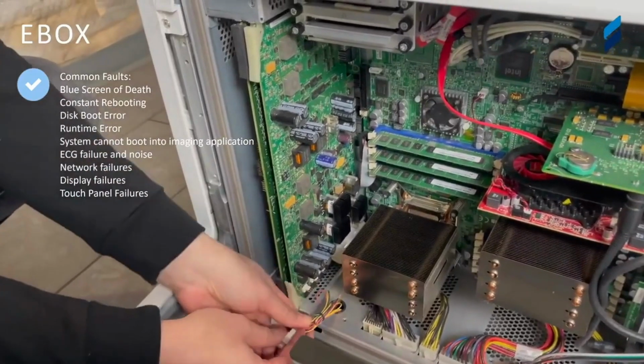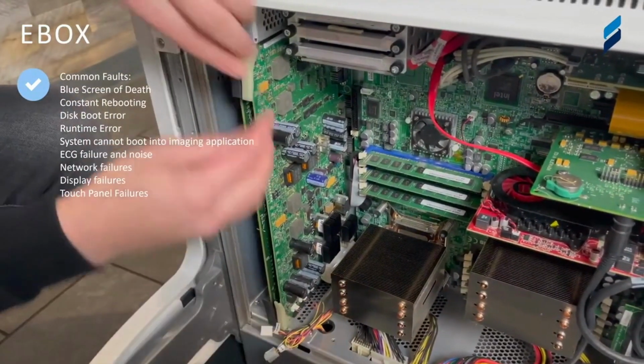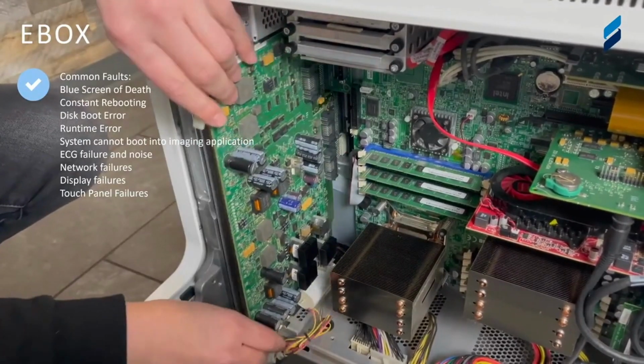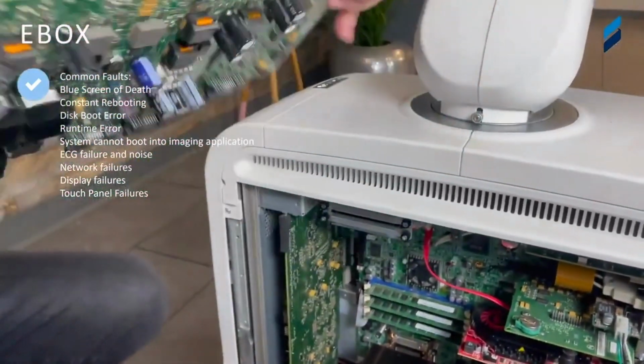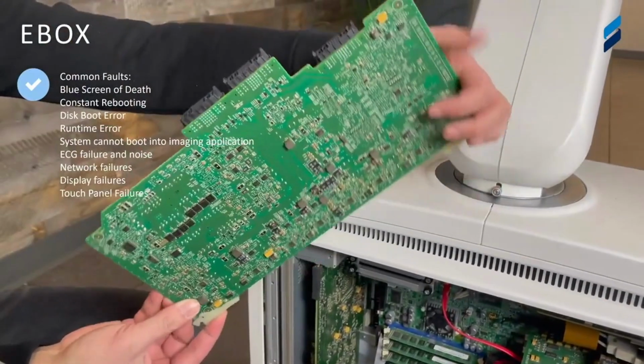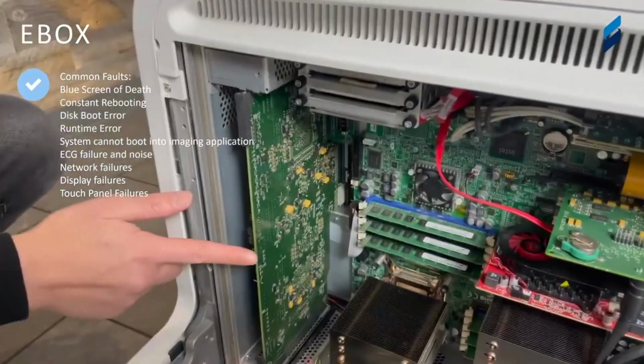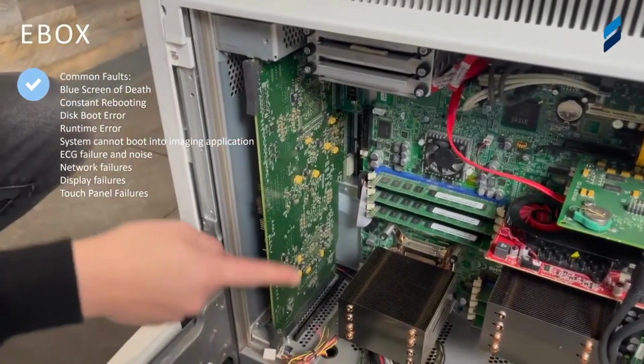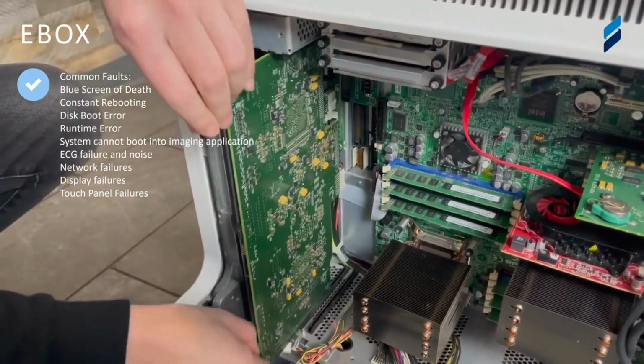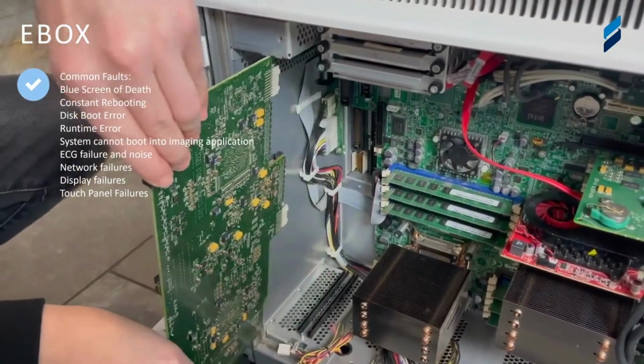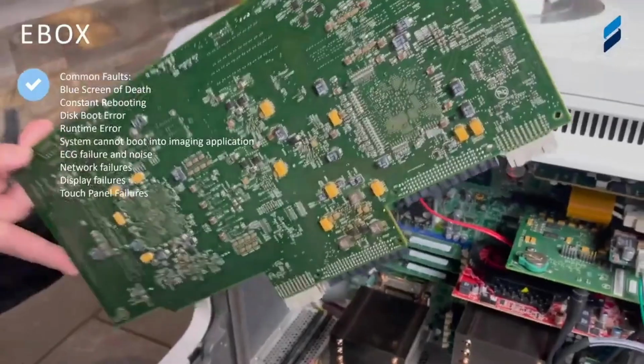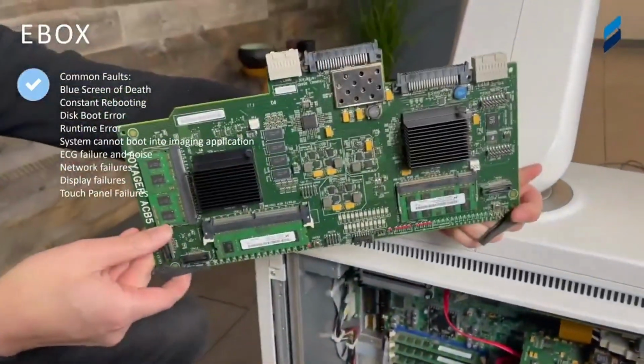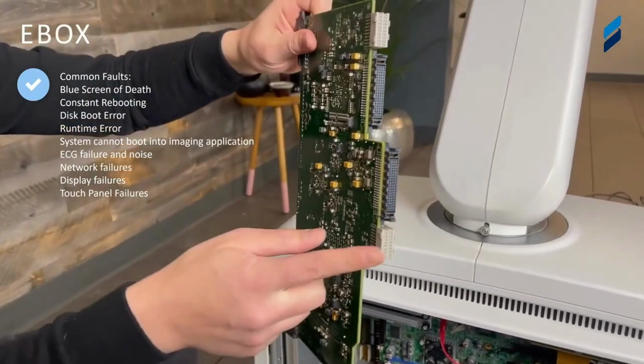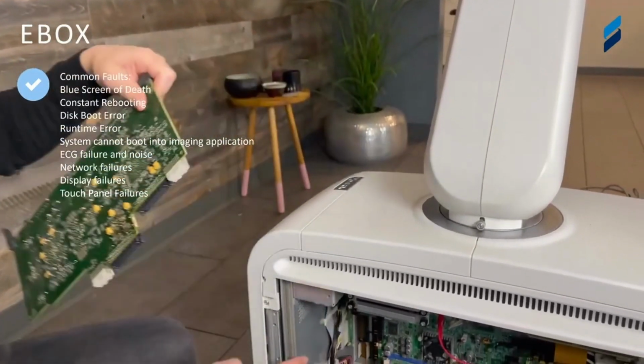And we have to remove these 2 cards. We're going to start with the power regulator board. Those are connectors down below for the fans of your system. And those fans obviously go down, pulling air from the bottom. That's our power regulator board coming out. And those connectors that we were just pointing at go to your acquisition module on the other side of that Ebox. So now here's our ACB. Also plugs into the acquisition module on the other side.